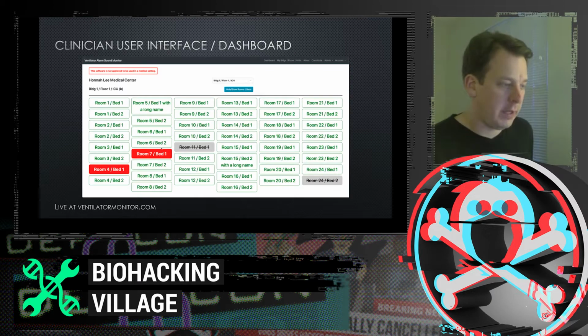We've got 3 states of a ventilator that we can display. The normal state, the happy state, is green. That means we're able to ping the ventilator, we're getting a good status report back, and there's no alarm. All is good. The second state is this gray strike-through box. That means we're not able to even connect with the ventilator, so a technician needs to go check on the ventilator. There's a fault in the system somewhere. The third state is this red box, and that'll actually flash. You'll see in the live demo. That means an alarm is currently being triggered on the ventilator, so the nurse needs to go check on it. So at a glance, the nurse can see, okay, I need to go check on 2 different ventilators, room 7 and room 4. I need to go check on those.